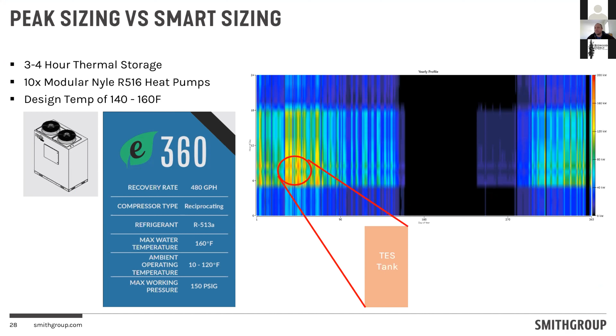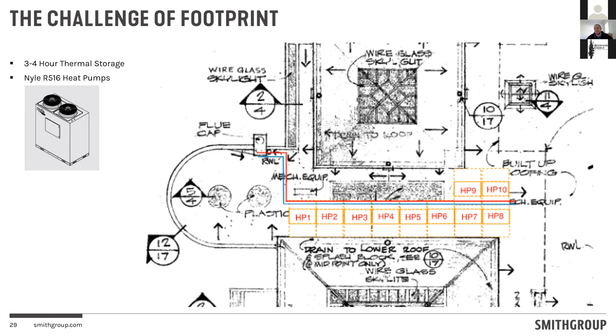When we start looking at footprints for all this equipment, air source heat pumps take up way more space than their fossil gas counterpart. So we need to be smart about the sizing of these systems, right-sizing them, and making sure that we can find a place for them to sit, especially in retrofit situations. As I mentioned earlier, we're on this constant drive to get to natural refrigerants, ammonia, CO2, et cetera.